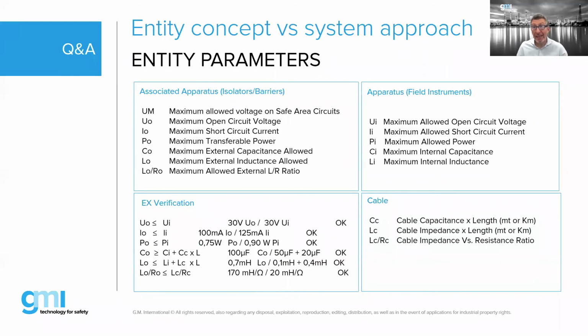It sounds complicated. It looks complicated. You've got a lot of parameters to check. So the basic concept, somebody posed the question earlier: a barrier is there to limit the energy going into the hazardous location within the curves that are defined in the standard. There is a maximum allowed energy, in fact not at the limit of the curves but 50% below. There's safety margin built in.